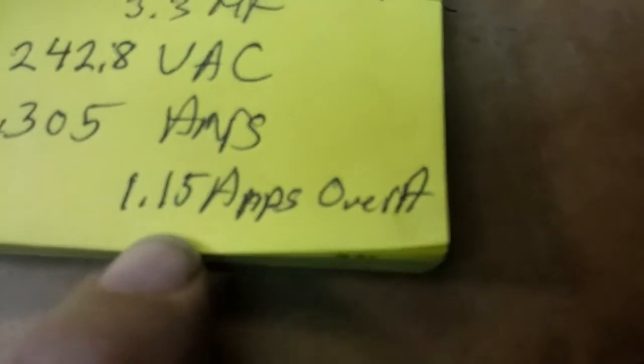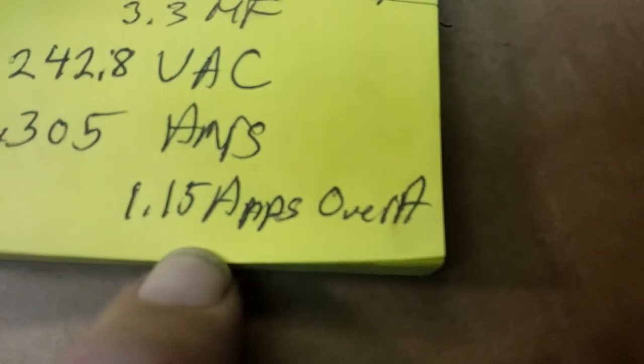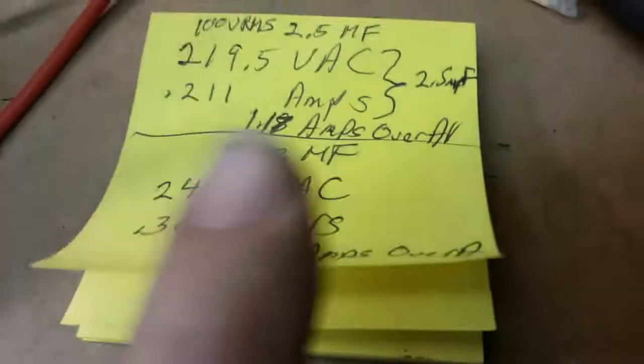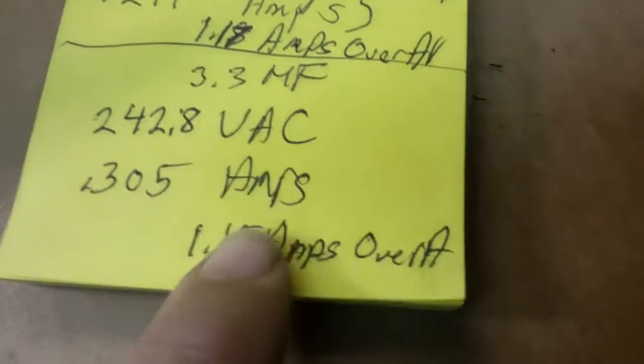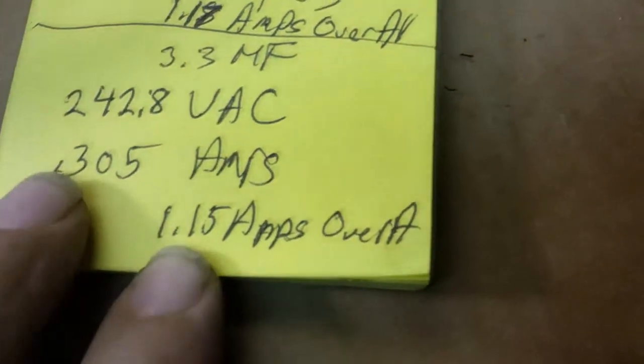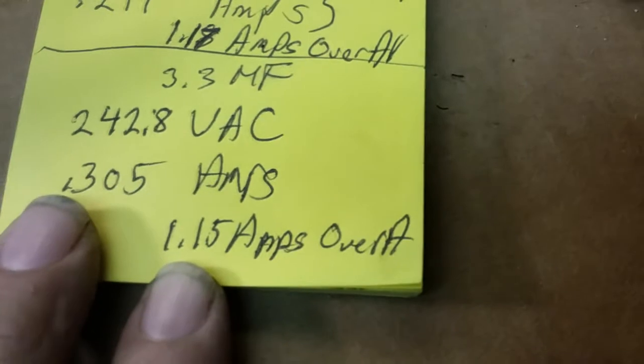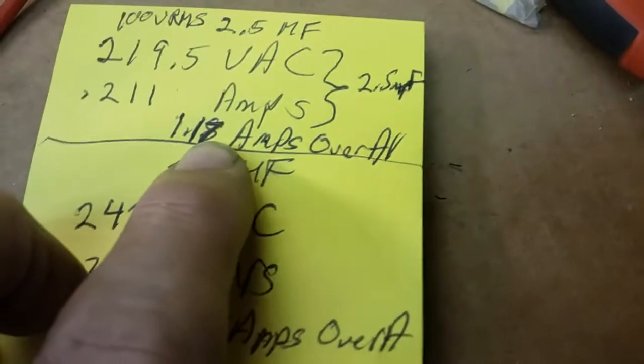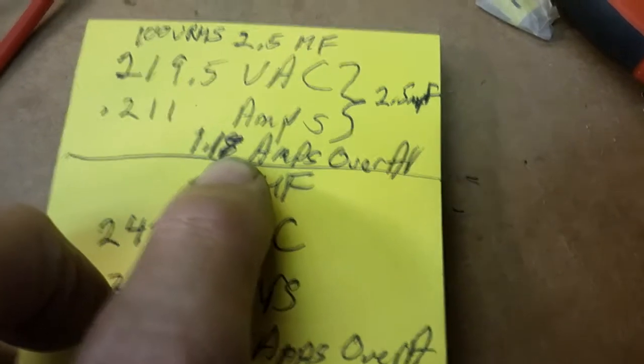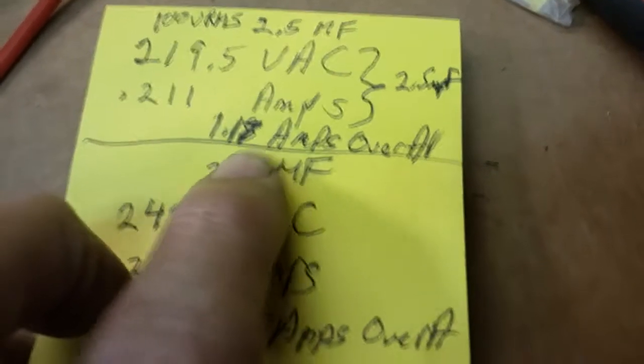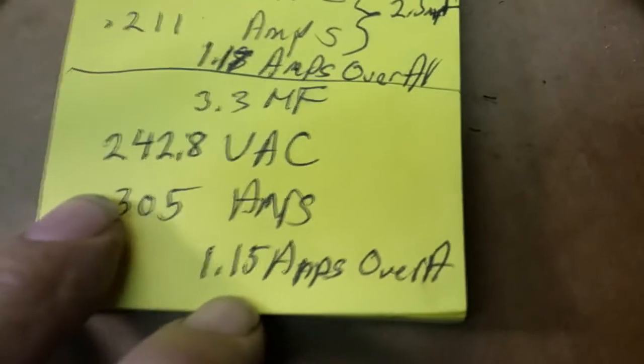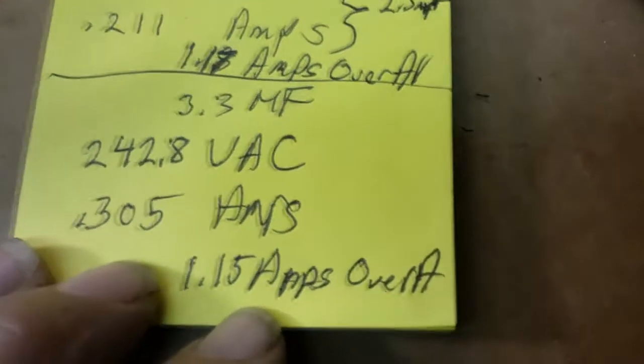As opposed to 85 to 95% of this capacitor. The overall current draw was a little bit less after I cleaned it with this capacitor. It was 1.15. This one's 1.18.